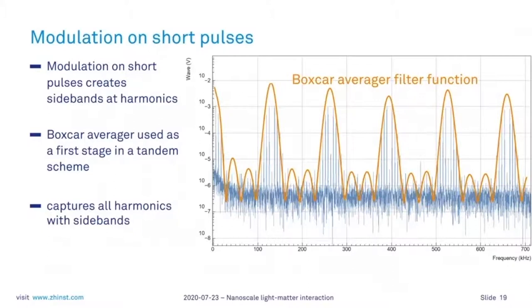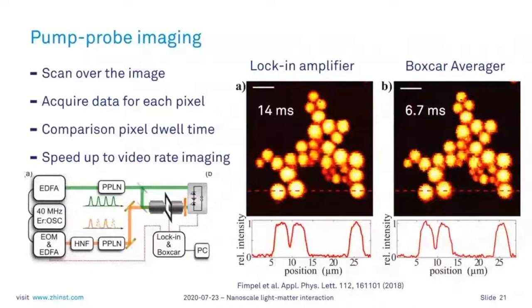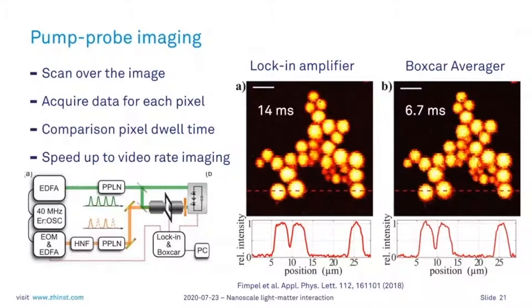To show an example where the boxcar averager is used: in typical pump-probe imaging with a confocal microscope, data is acquired for every pixel across the entire scanned image. In this work, images were recorded for the same signal-to-noise ratio and the pixel dwell time was compared. The boxcar was able to improve measurement time by more than a factor of two — very important for achieving fast video rates or saving precious measurement time.